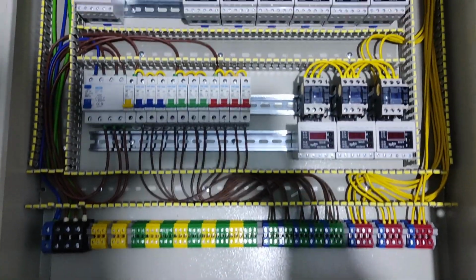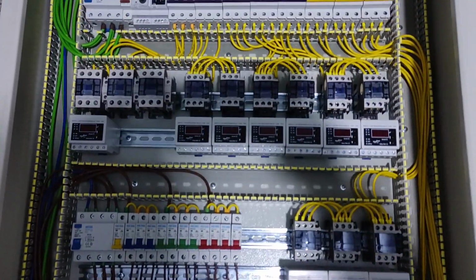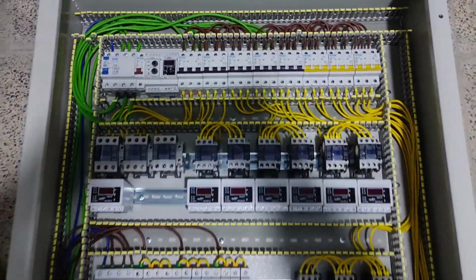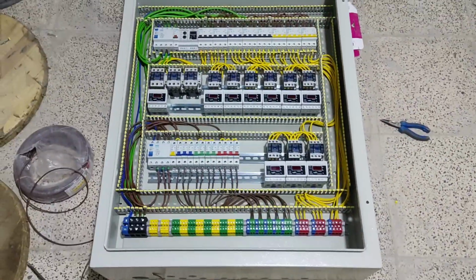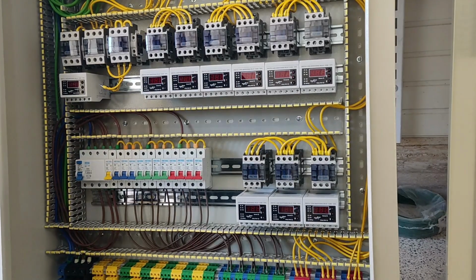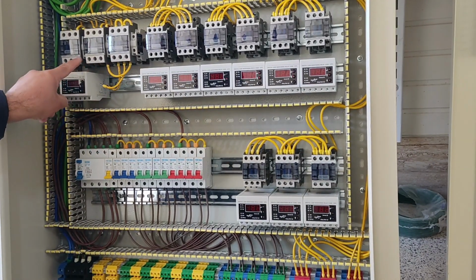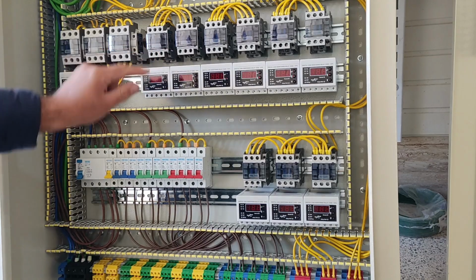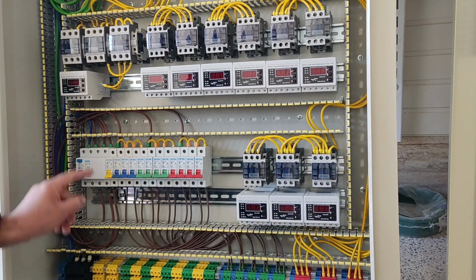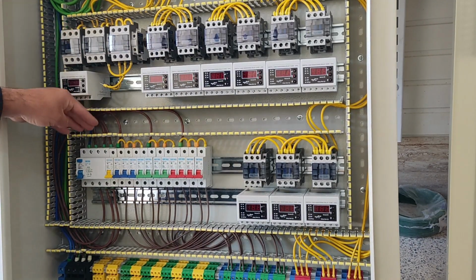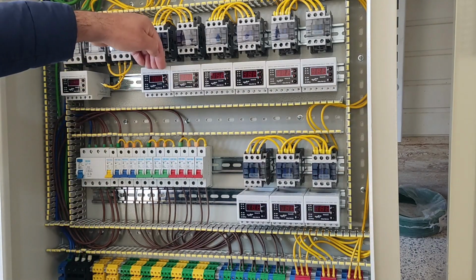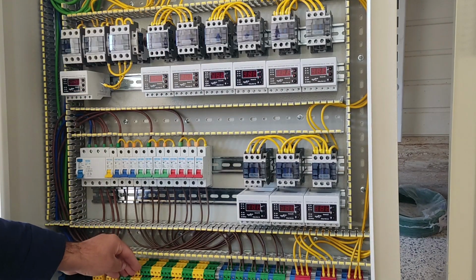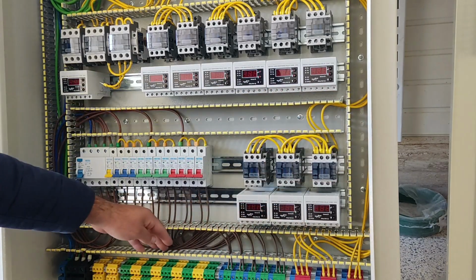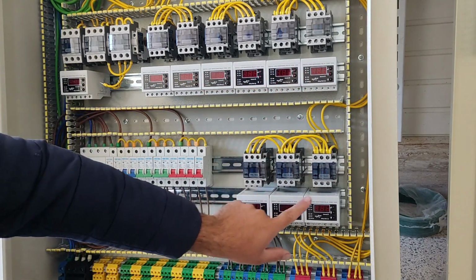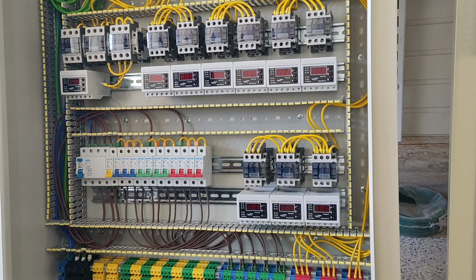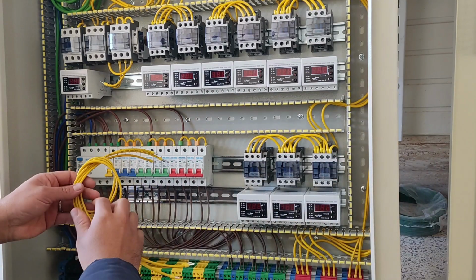Please look carefully to the wiring. Now we connect the outputs of each contactor to the output terminals. But before that, we pass the three phases through the whole of the current controller relay so that the output current from all three phases can be measured, and if the excess current passes, it will cut off the circuit, and we repeat this work for all three-phase contactor outputs.